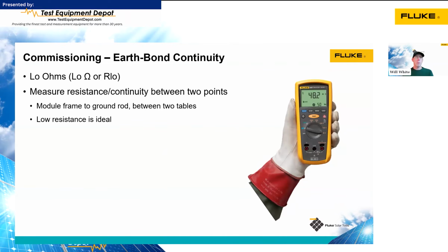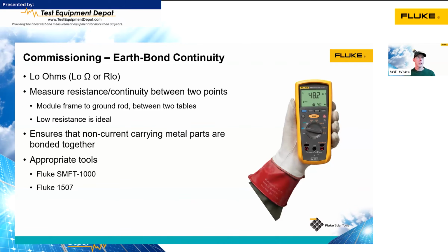Another test done at commissioning is earth bond continuity. This is making sure that all of our metal parts are electrically connected together. Things like module frames, racking, metal conduit, metal junction boxes, combiner boxes, inverters, cabinets, our medium voltage transformer cabinets, battery cabinets. All those things that don't usually carry current need to be electrically bonded together so that if there's ever a fault, that fault has an easy path to ground that's not through the technician working on the system. We're looking for low resistance in this case. So typically looking for 0.5 ohm or less resistance there.